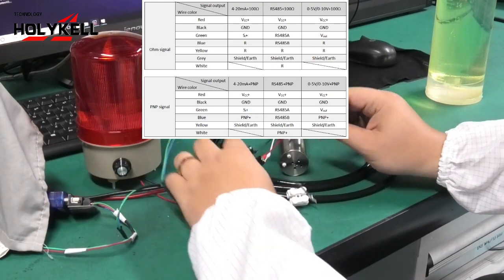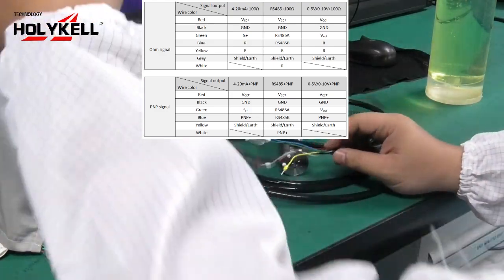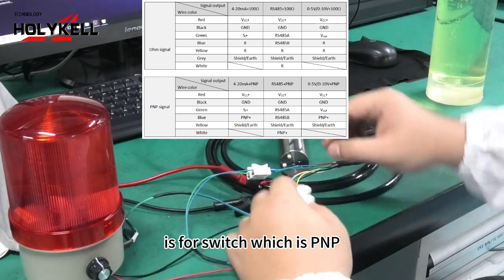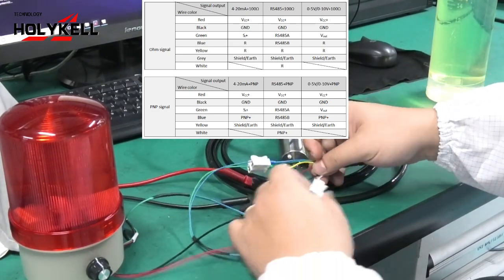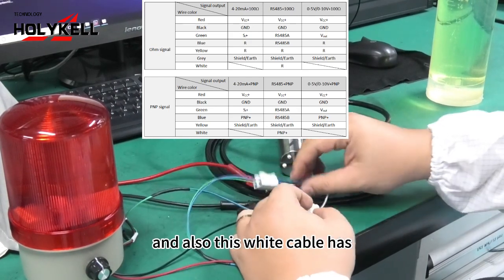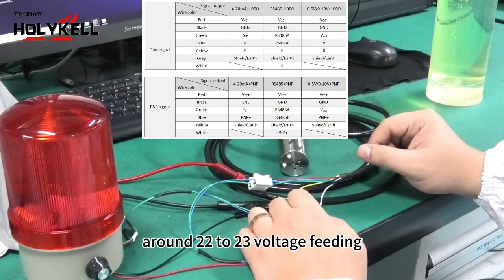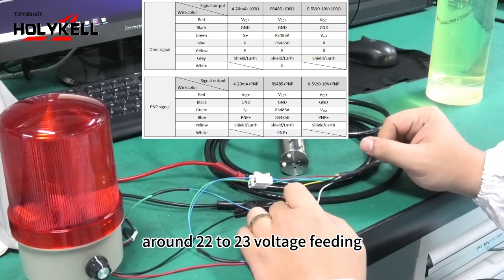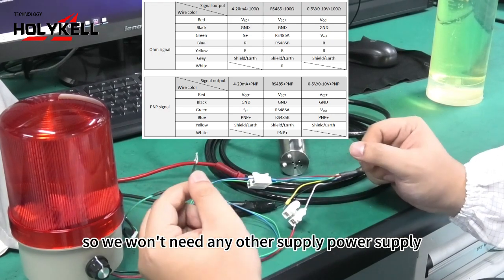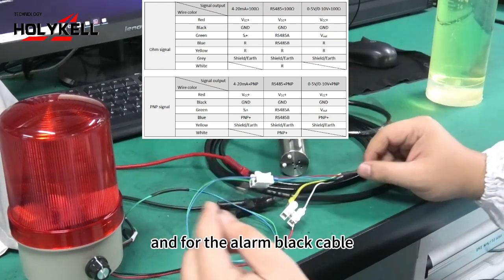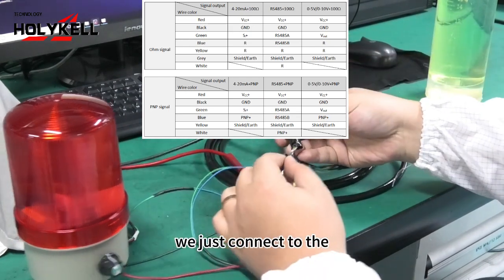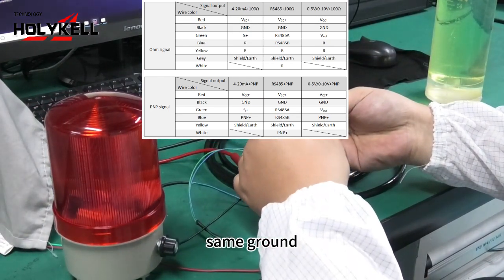The white cable is for the switch, which is PNP. This white cable has around 22 to 23-volt feeding, so we won't need any other power supply. For the alarm black cable, we just connect to the same ground.